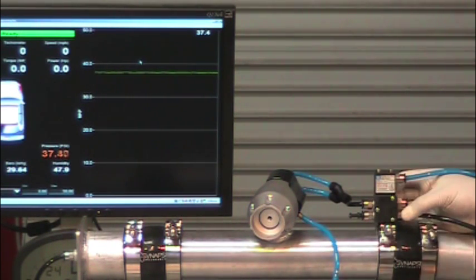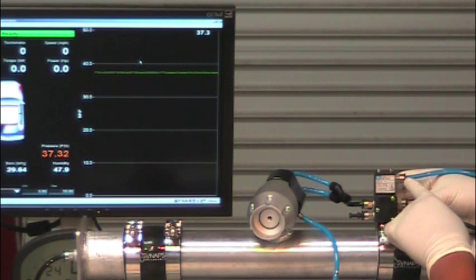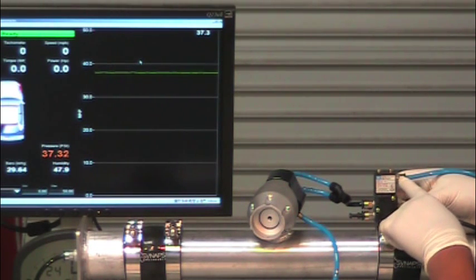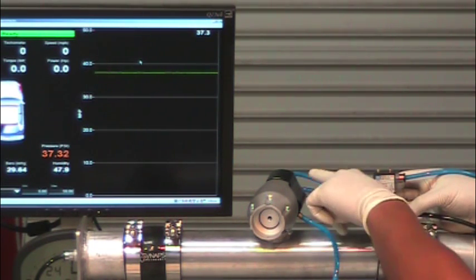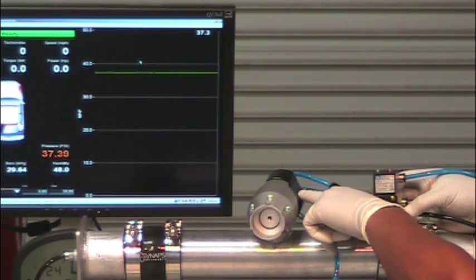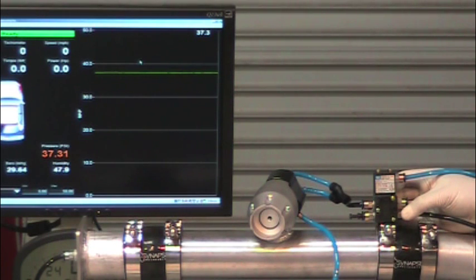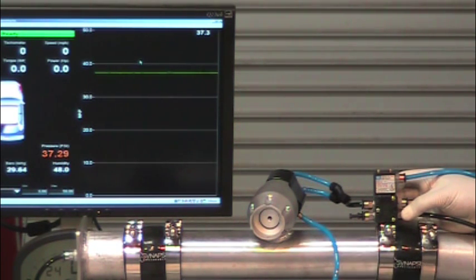So now the valve's control pressure is keeping the valve shut. Once we let this pressure go, the pilot pressure will disappear. It will bring the back of the pressure relief valve to atmosphere. And there will still be pressure in the pipe.